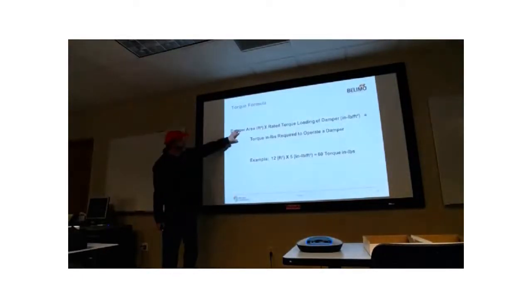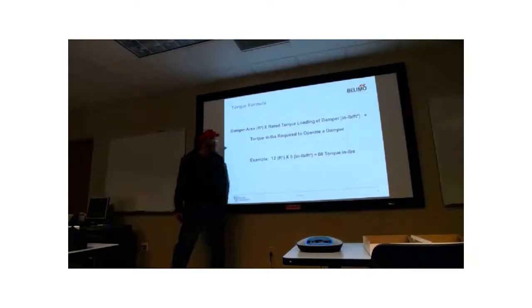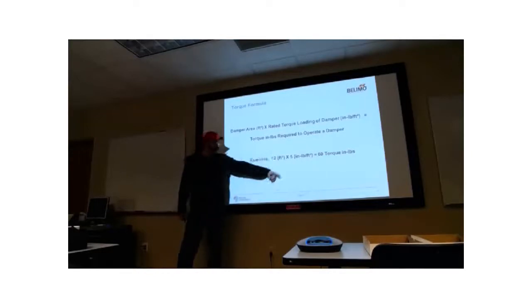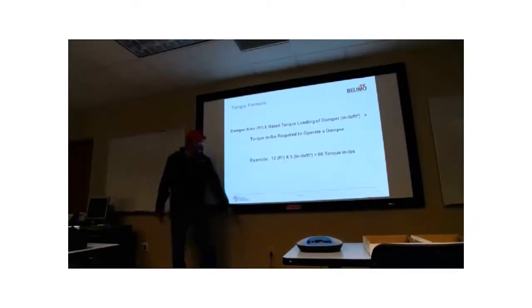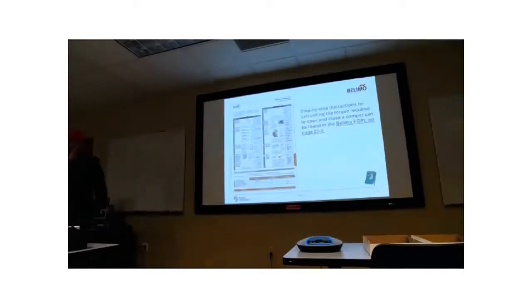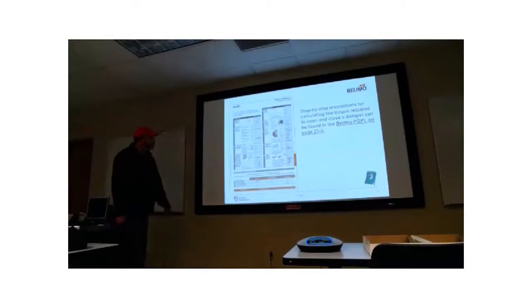So if you take the damper area in square feet, you multiply it by the torque loading factor in inch-pounds per square foot, you come up with the torque in inch-pounds. So 12 square foot damper, if your loading factor is 5 inch-pounds per square foot, 12 times 5 is 60. We're going to have our own little example here we're going to go through.